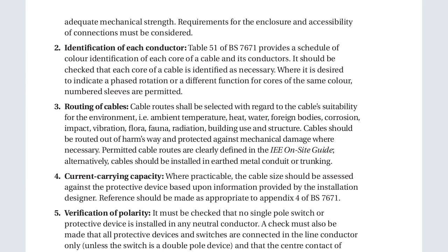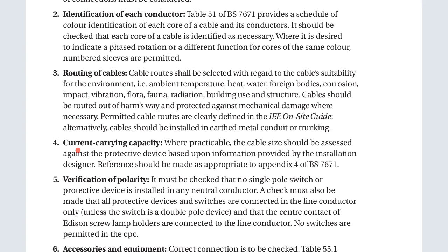That is, Table 51 of the BS standard, BS 7671, provides a schedule of the color identification of each core of cable and its conductor. So it should be checked that each core of the cable is identified as necessary, where it is desired to indicate the phase rotation or a different function for cores of the same color. Another one is the routing of cables.